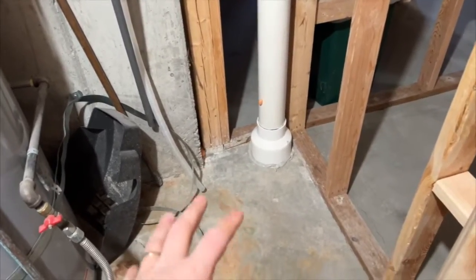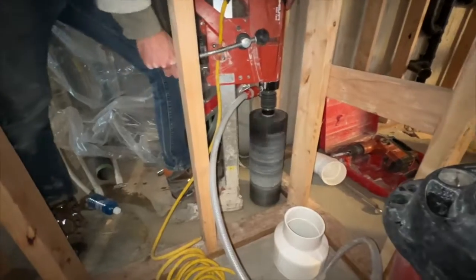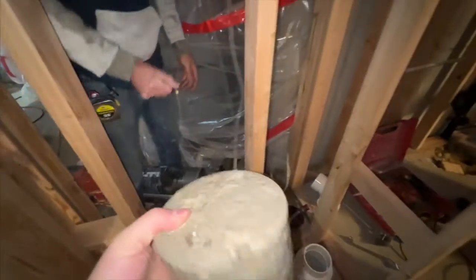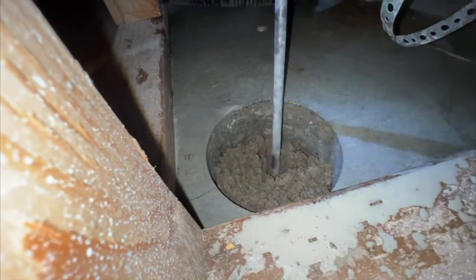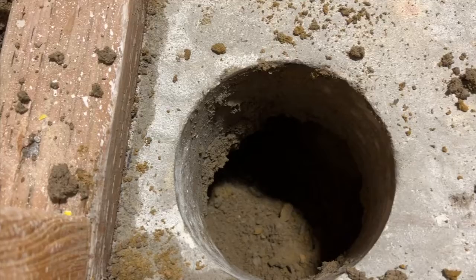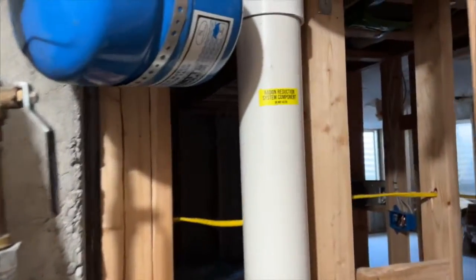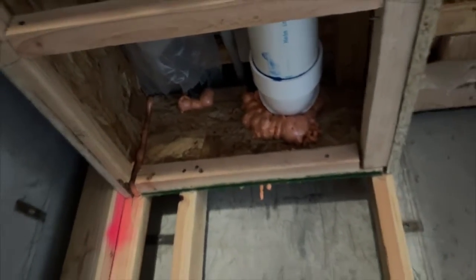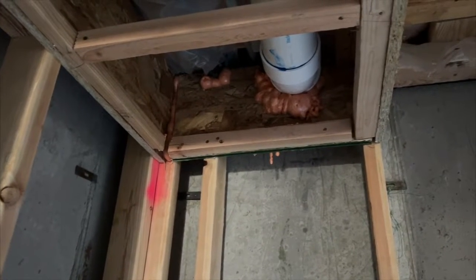Because the radon comes from below the ground, what we do is core a six-inch hole in the concrete. Then we use PVC pipe to connect to it, and underneath the ground we drill out and remove as much dirt as we can to create a space where the vacuum can suck gases from beneath the home up and into the pipe. This whole pipe is pressurized with a negative pressure and is labeled as a radon reduction system component. The pipe system runs along here and up and out of the home, following along the ceiling, making a turn, continuing out through the house and garage, and up to the roof where it's exhausted into the air outside.